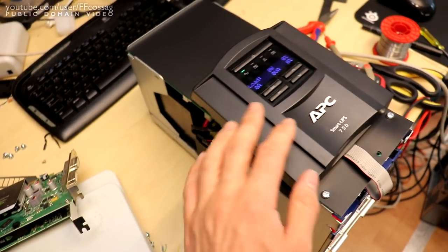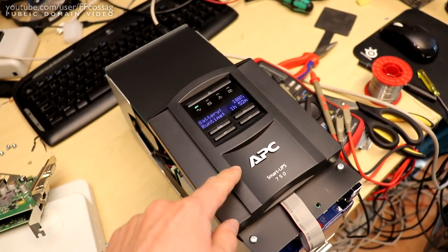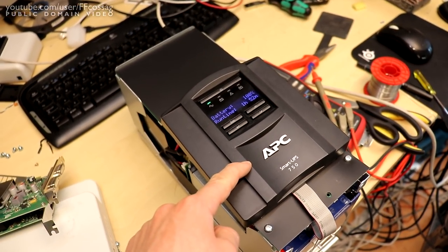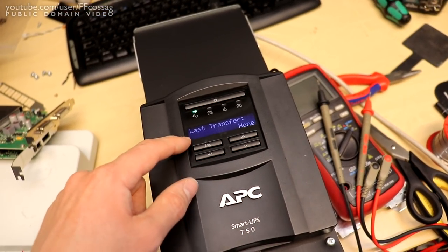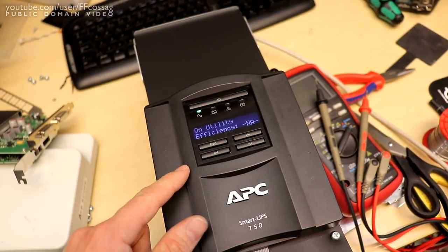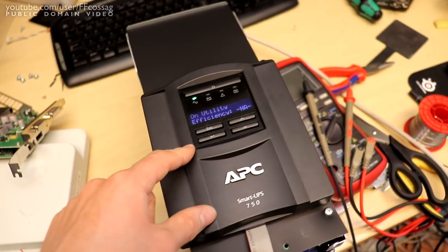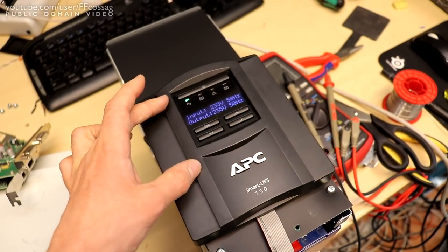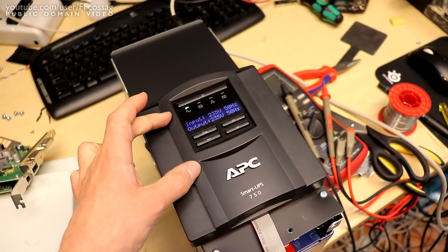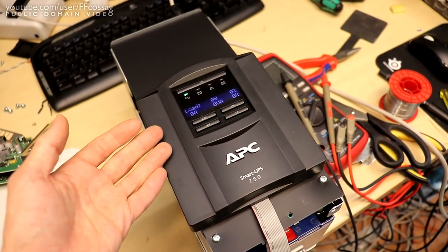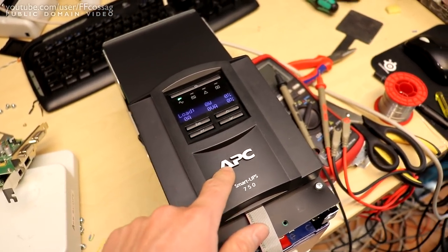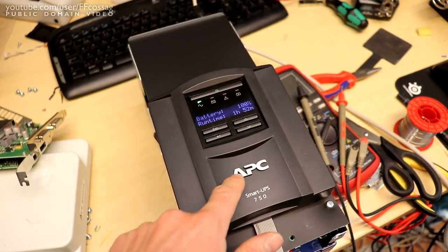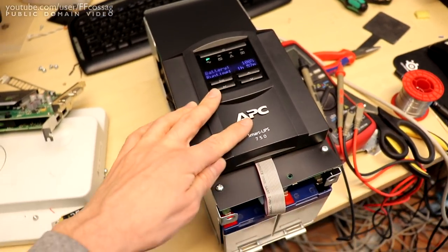Running this thing, I can tell you a couple of differences between this and the previous model. This seems to be a 2009 year SMT 750i. This has the green mode feature. This will actually go into offline UPS mode, it'll turn off the transformer after a few hours of good power, reducing the power consumption considerably. That's something I like a lot.